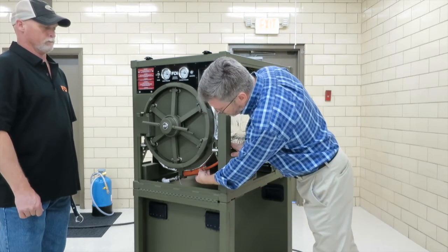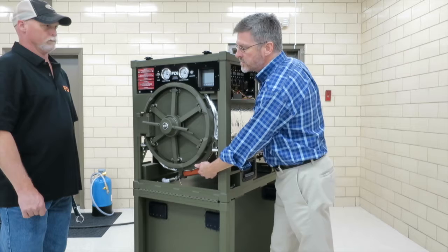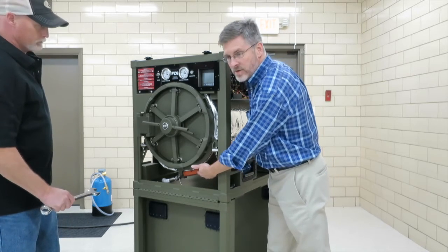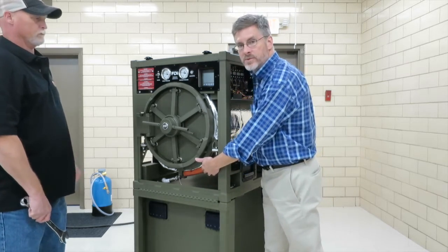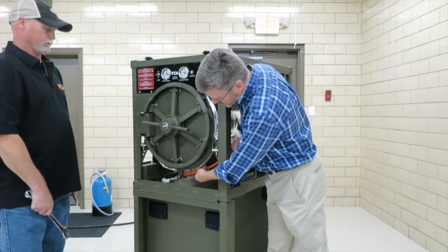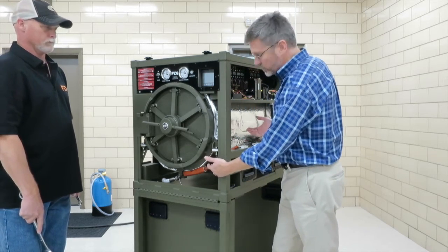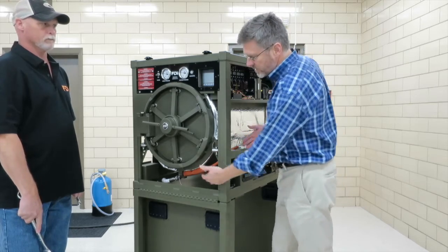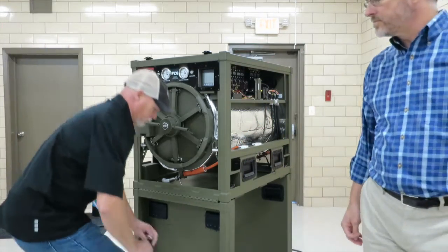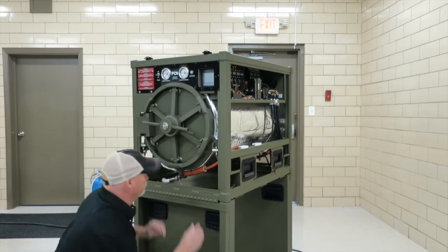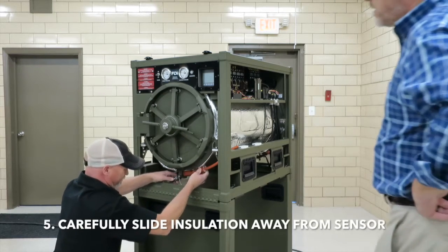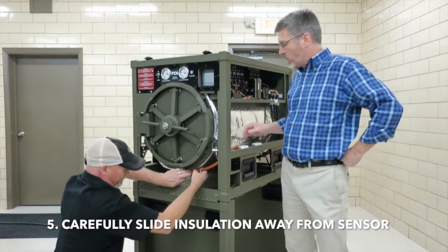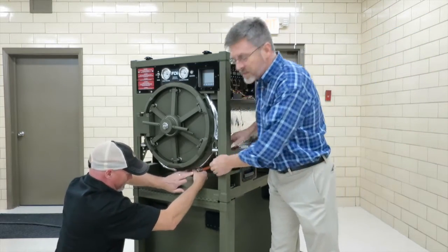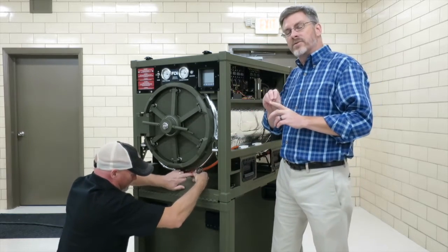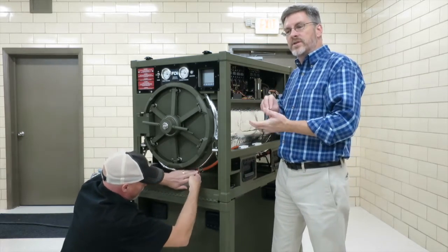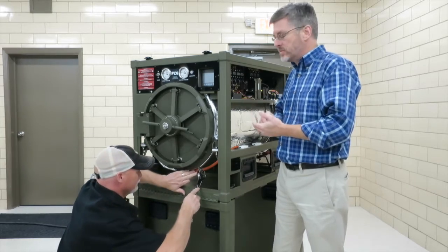So we're going to pull this back. We're going to use a couple of wrenches. I think we've got a 9/16 to loosen it with, and another one to counter torque, very important. So we're going to take that off. We'll show you what the actual spare part looks like with this section right here. As he's doing that, you need to be real careful. There's wires here. There's a cable that comes down, and the probe is about 6 inches long, and at the back of the probe, there's heat shrink, and there's wires. We just need to be real careful with this.